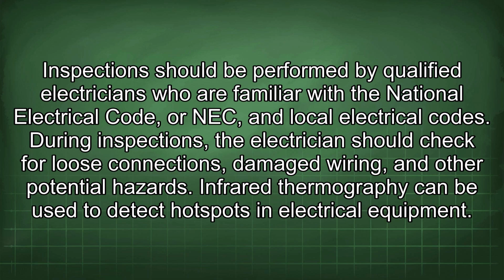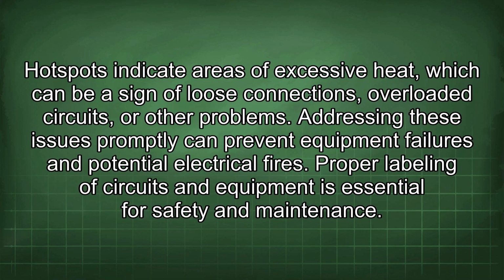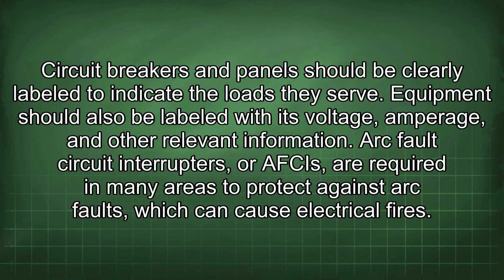Infrared thermography can be used to detect hotspots in electrical equipment. Hotspots indicate areas of excessive heat, which can be a sign of loose connections, overloaded circuits, or other problems. Addressing these issues promptly can prevent equipment failures and potential electrical fires. Proper labeling of circuits and equipment is essential for safety and maintenance. Circuit breakers and panels should be clearly labeled to indicate the loads they serve. Equipment should also be labeled with its voltage, amperage, and other relevant information. Arc fault circuit interrupters, or AFCIs, are required in many areas to protect against arc faults, which can cause electrical fires.